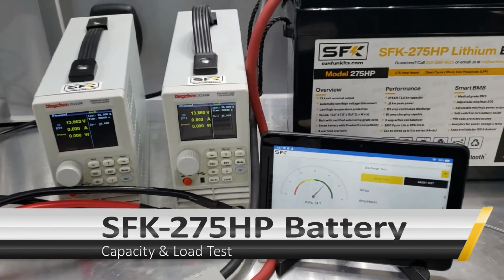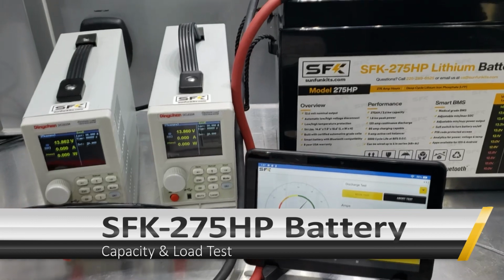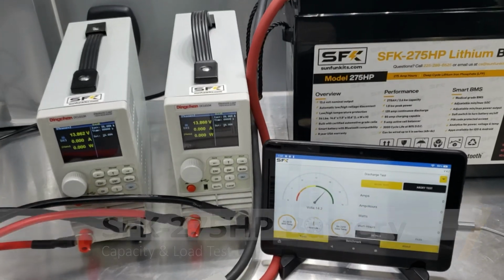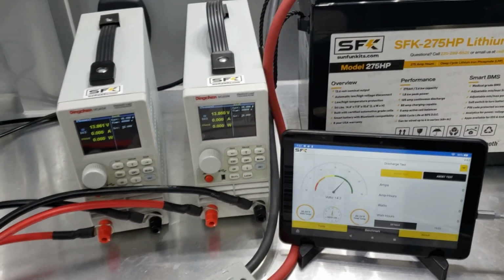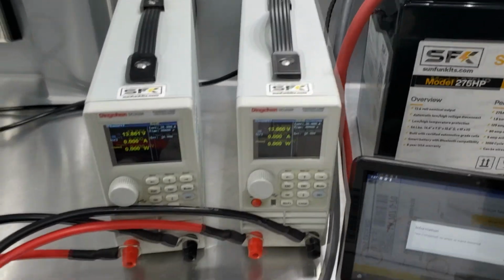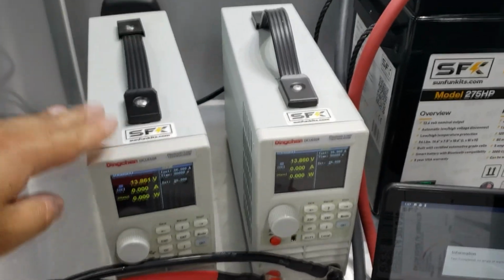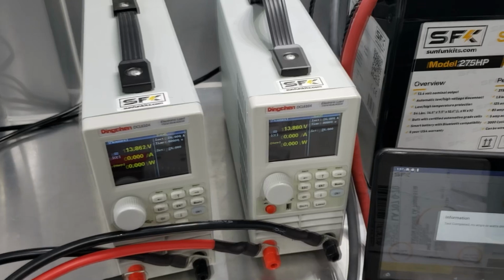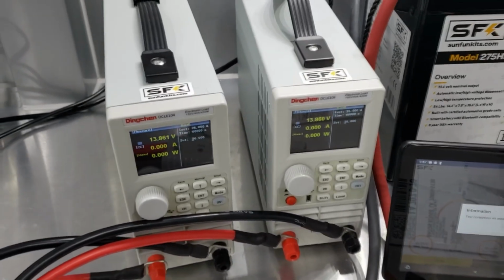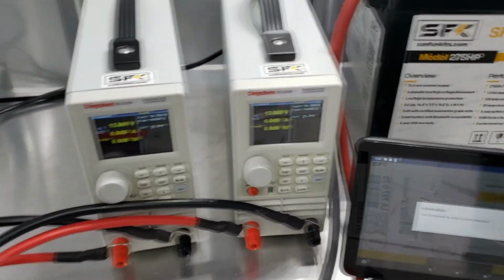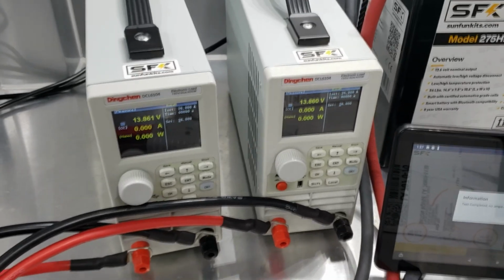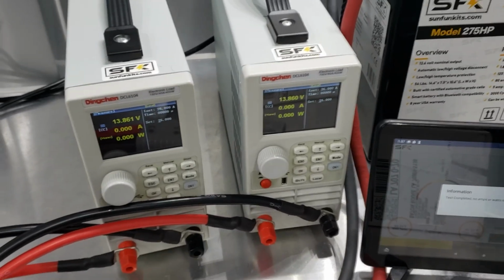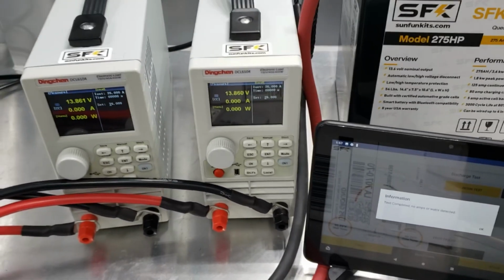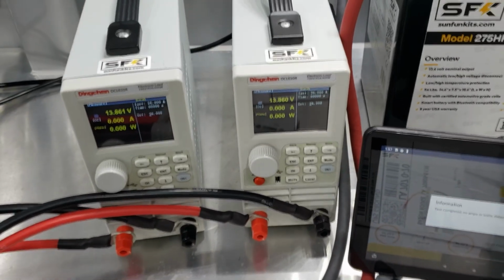Today we're going to do a load test or a capacity test on one of the 275 HP batteries. This test is a little different, we're using our mobile electronic loads. These devices help us test batteries in the field. They're not as powerful as our big rack-mounted electronic load, but they give us a pretty good idea. You can also gang two together to get a combined load output.